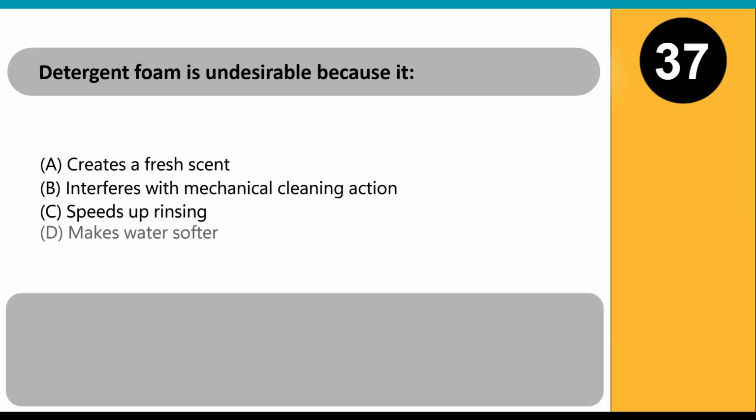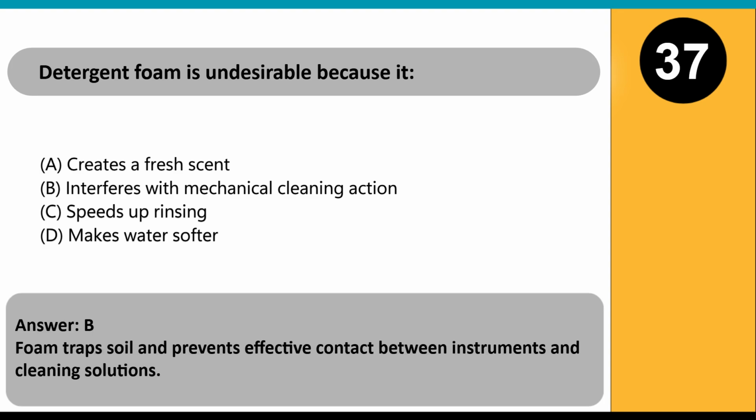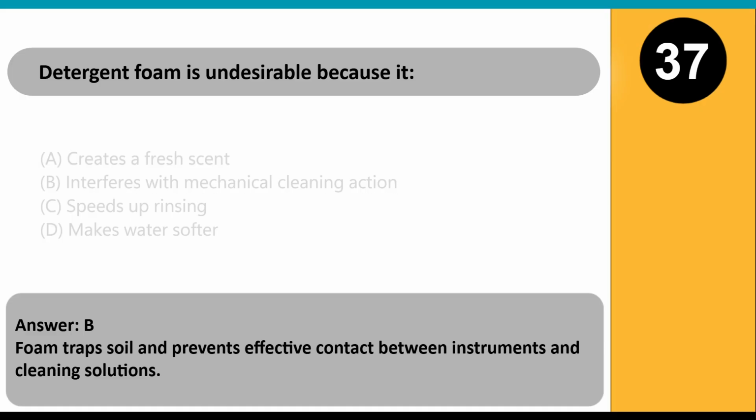Detergent foam is undesirable because it: A. Creates a fresh scent. B. Interferes with mechanical cleaning action. C. Speeds up rinsing. D. Makes water softer. Answer, B. Foam traps soil and prevents effective contact between instruments and cleaning solutions.